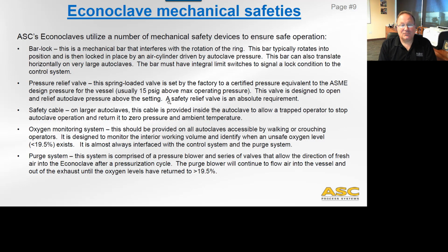Oxygen monitoring systems, these have been more and more a standard thing in the last 10 years on autoclaves and large autoclaves. This is provided for any autoclave where an operator regularly walks into or gets into an autoclave in either a standing or crouching mode. And basically, it's designed to monitor the interior working volume and identify whether a safe or unsafe condition for oxygen exists. And 19.5% is the OSHA level for a safe oxygen environment. So above 19.5, everything's good. Below 19.5, it's considered unsafe, and as you get lower and lower, it will go from being confused and woozy to being dead at about 6% oxygen.